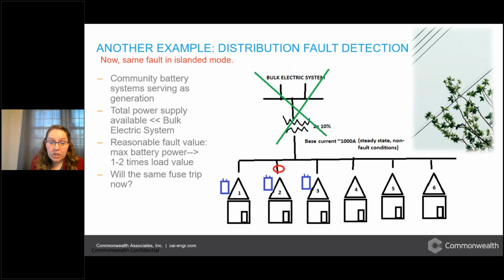Very cool. We could still have 1,000 amps of current flowing around this area, but it's also possible that our batteries are near their max generating power to supply that 1,000 amps. So they're doing well, but they're almost maxed out on how much power they can be pushing through. If a tree falls in the same spot, circled in red, we might see way less fault current coming into that area. That means we still have a problem. We still have current leaking out of our system. It's inefficient, and it could be unsafe because we're not able to control the flow of current anymore. That means we need to eliminate this problem. We need to clear the fault. We need to isolate that section of the line.